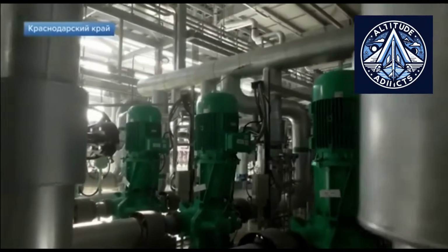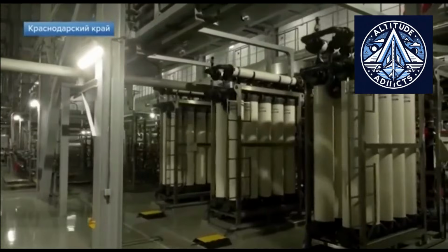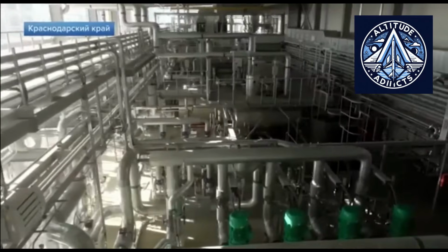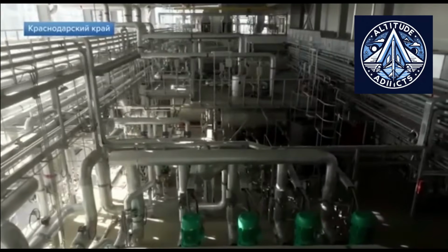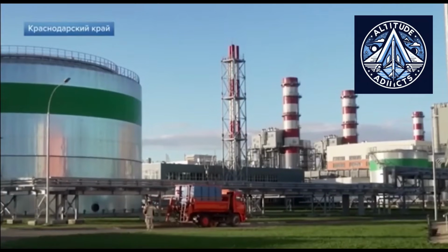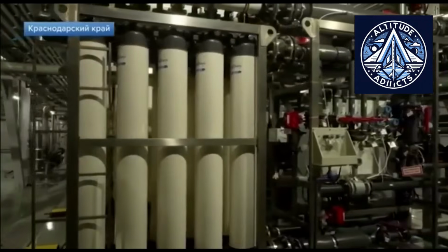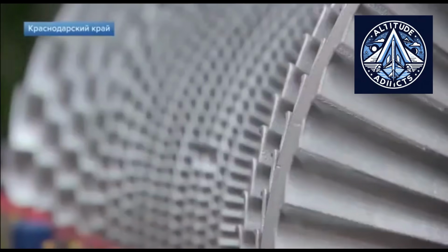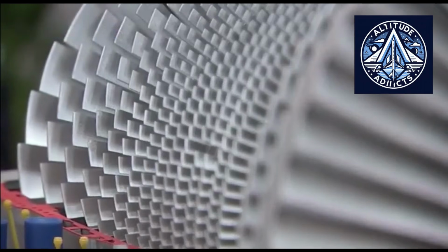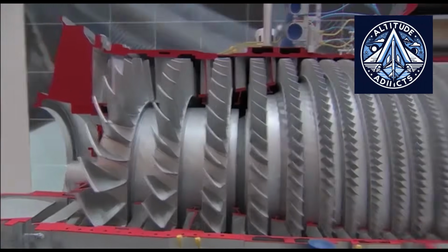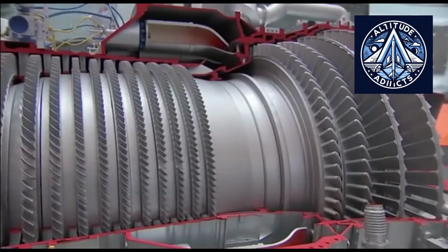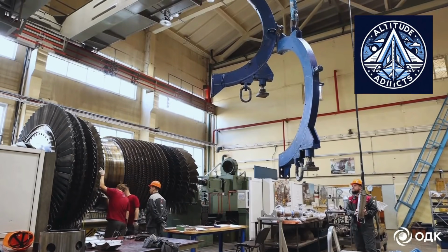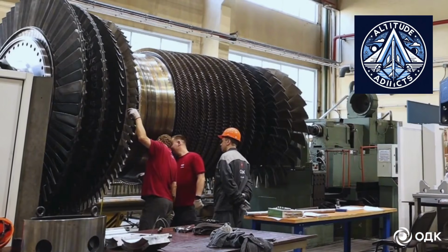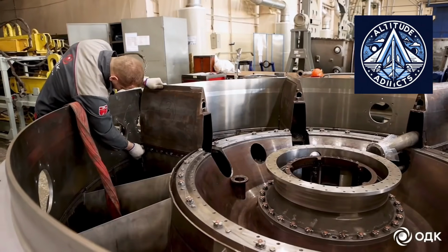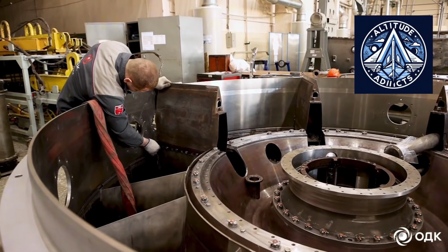This turbine's output shaft rotates at the industry-standard speed of 3,000 revolutions per minute for grid-connected electricity generation, while exhaust gas exits the turbine at a mass flow of 371 kilograms per second and a temperature of approximately 517 degrees Celsius. In simple cycle operation, the turbine attains an efficiency of approximately 36%.